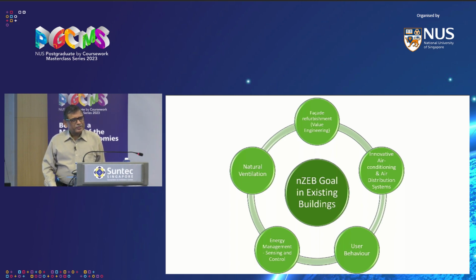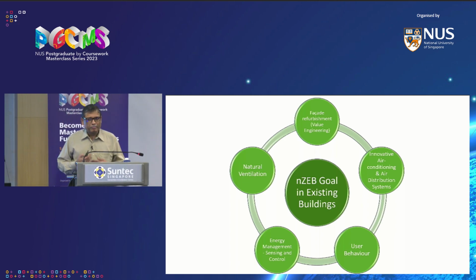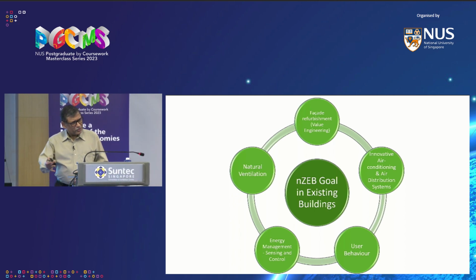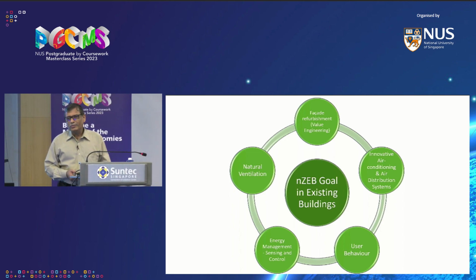Coming to the last couple of slides, just to sum up my main messaging here. If we are thinking about existing buildings, it's doable. As you can see in this slide, we worked on that SDE 1 and 3 by improving the facade. The window system in the old building, a 45-year-old design, was quite poor and leaky. We removed the entire window system and went in for more energy efficient panels. Good glazing material, good window material, good panels, no leaks, that kind of a design feature.